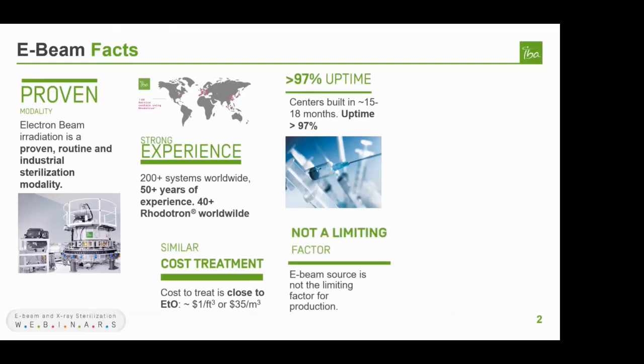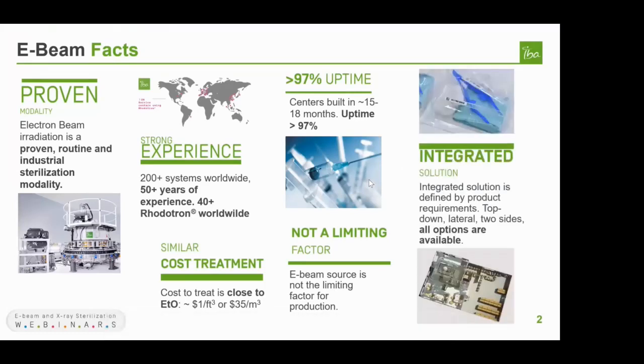The power of the electron beam source itself is not typically the limiting factor for throughput. These are integrated systems, and other components are critical to maximizing the rate of sterilization. Optimizing those other components can enable consideration of a higher powered source to increase production. The shape an integrated solution takes is defined by the products and the requirements set by the user. There's no single system configuration when it comes to electron beam sterilization. As always, start with the products.